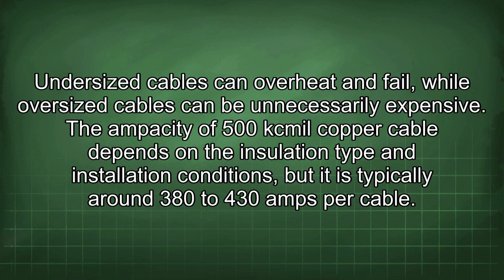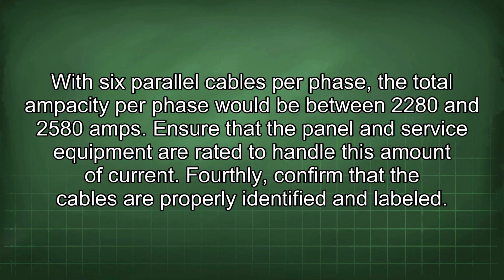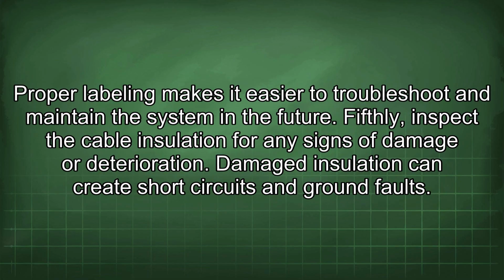The ampacity of 500 kcmil copper cable depends on the insulation type and installation conditions, but it is typically around 380 to 430 amps per cable. With 6 parallel cables per phase, the total ampacity per phase would be between 2280 and 2580 amps. Ensure that the panel and service equipment are rated to handle this amount of current. Fourthly, confirm that the cables are properly identified and labeled. Proper labeling makes it easier to troubleshoot and maintain the system in the future.